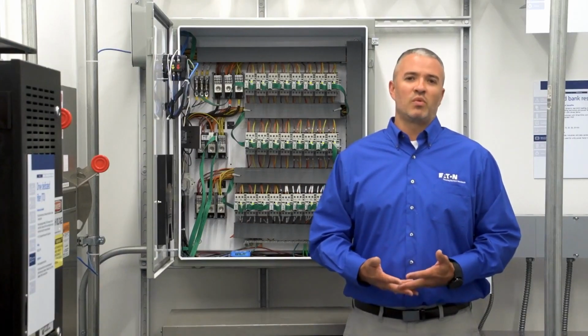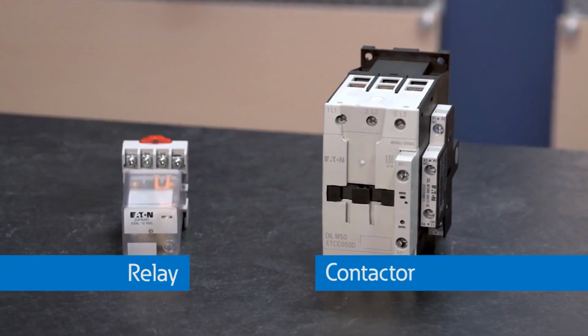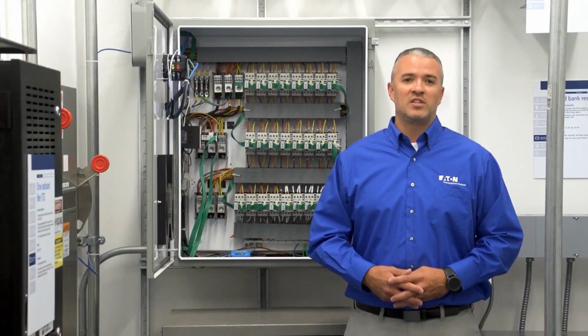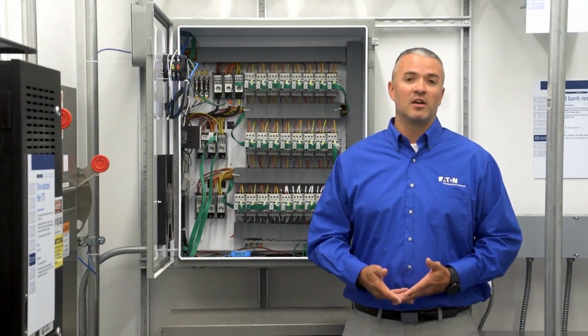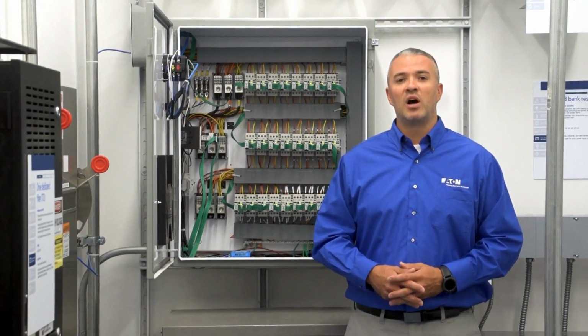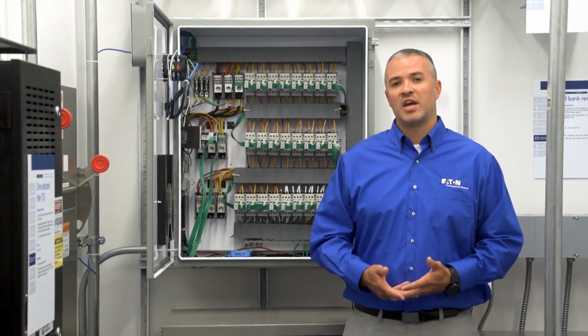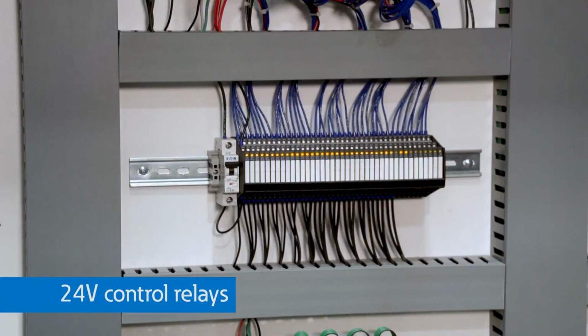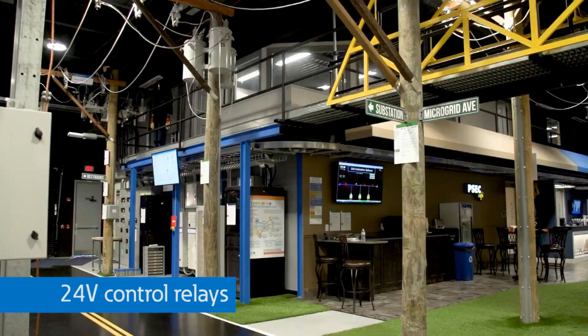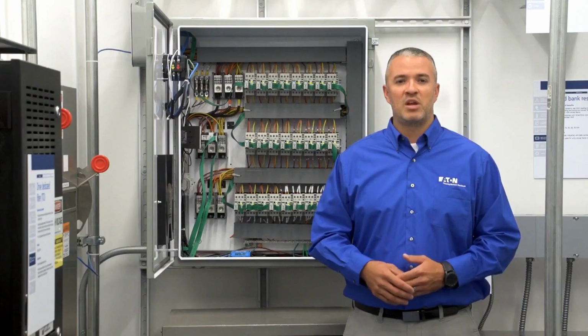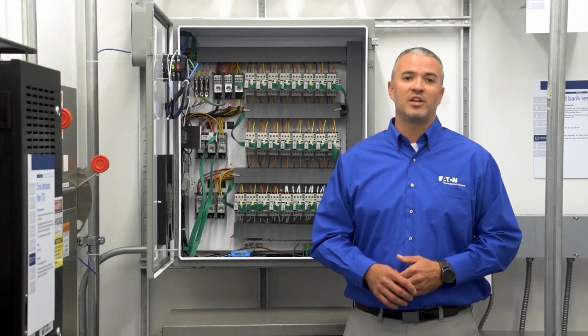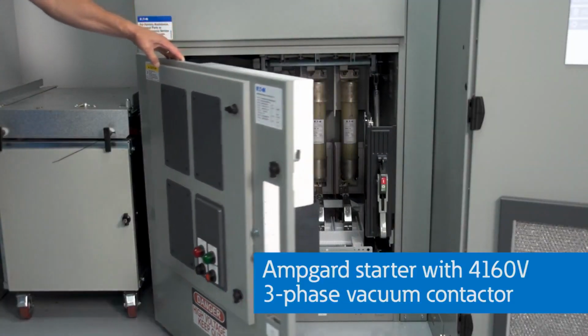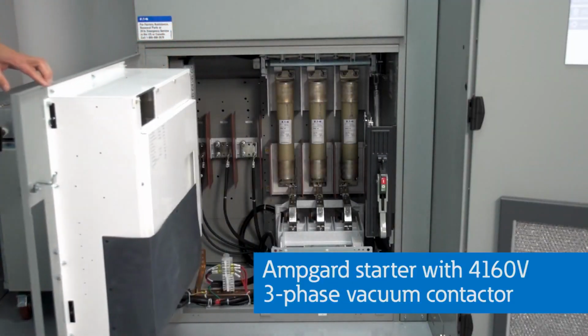What is the difference between a relay and a contactor? While both are electromechanical devices and operate in a very similar manner, you can think of a relay as a smaller, less expensive version of a contactor. Relays will generally be used to switch lower single-phase voltages and current levels that may not exceed 20 amps, while contactors can switch thousands of amps in low and medium voltage three-phase systems.